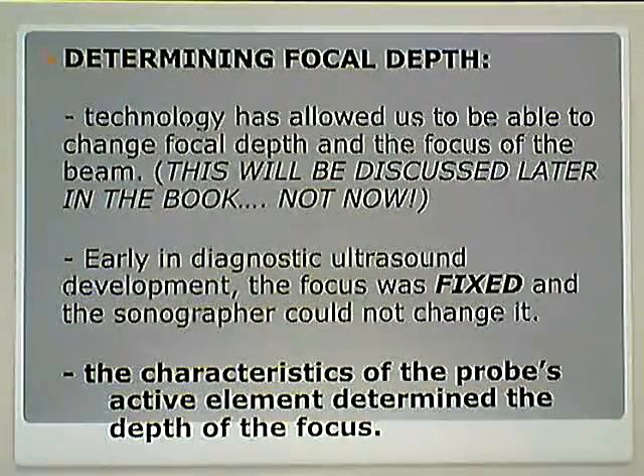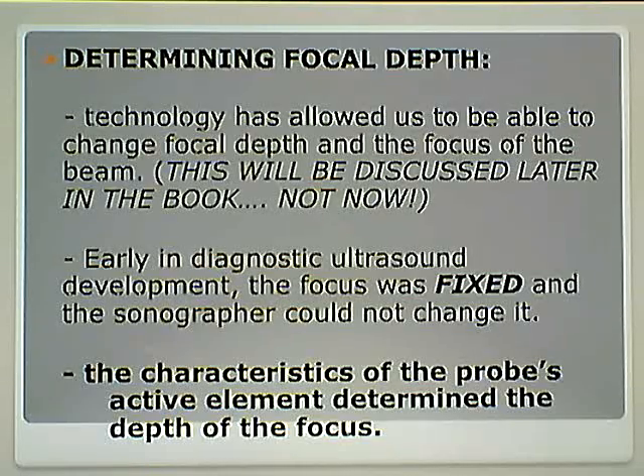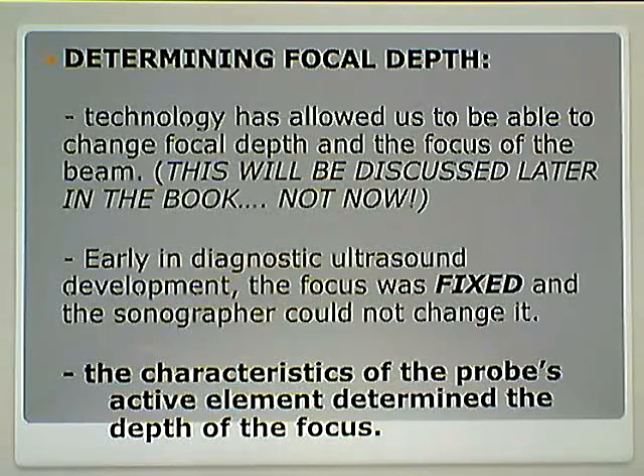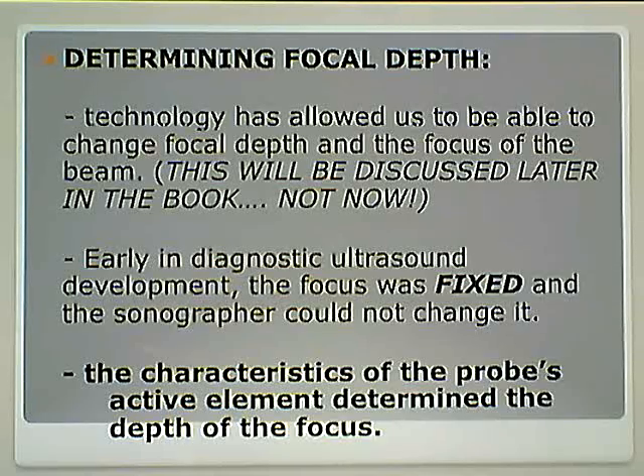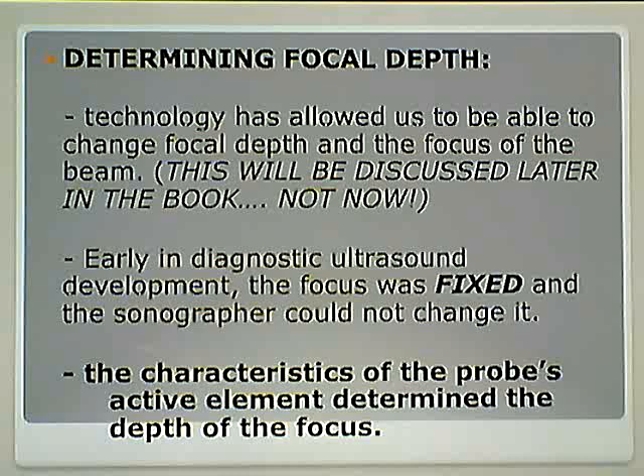Moving right along — determining focal depth. Technology has allowed us to change the focal depth and the focus of the beam, but we're not going to talk about that in detail right now. Early in diagnostic ultrasound development, the focus was fixed, depending on the characteristics of the active element or crystal. It was a fixed focus; we couldn't change it.